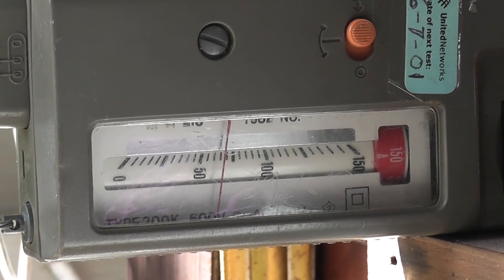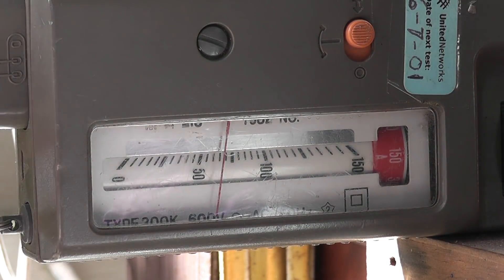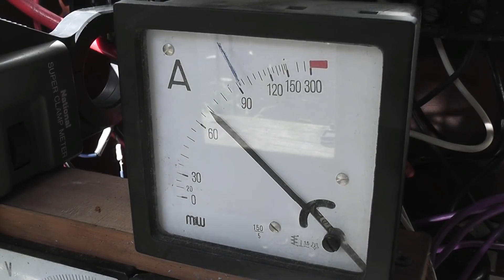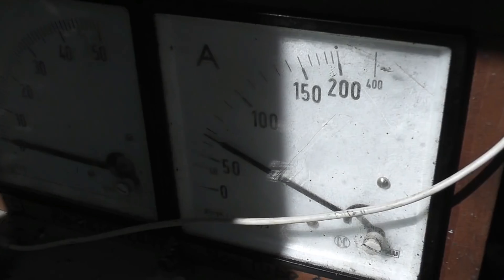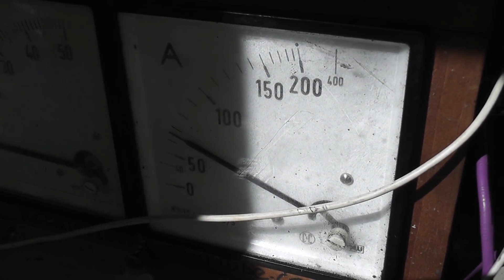I'll get a better close-up on the dial — it's pretty dark. I'll flick it back to the 60 scale so we'll go full. The load is about 70 ampere here, so it's off the scale. Beautiful little instrument. So the load measured here is about 60 to 75 ampere — more or less the same on this meter. Pity about the shade but hopefully it's visible.